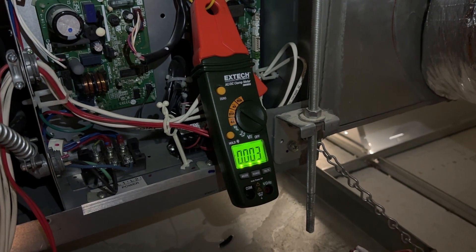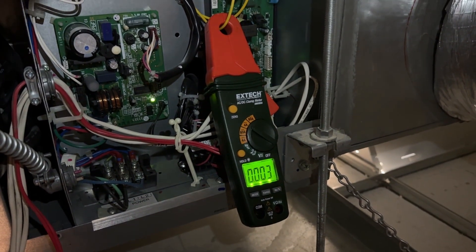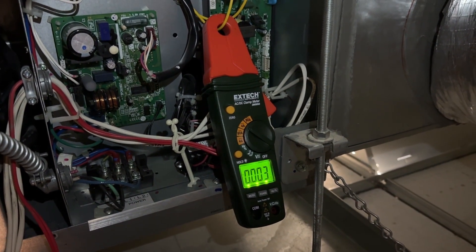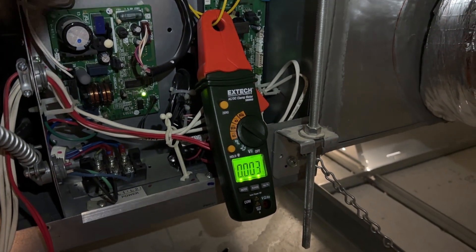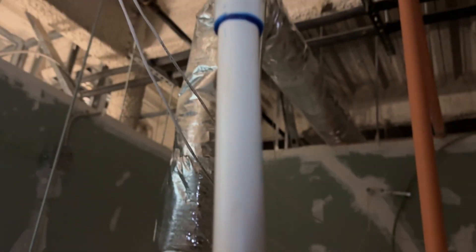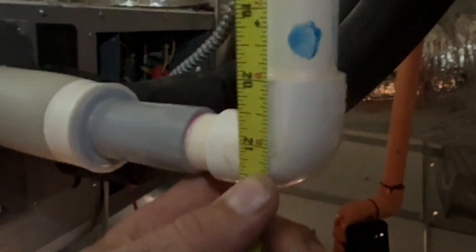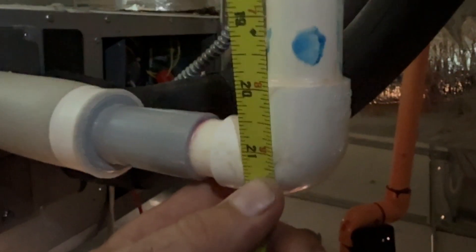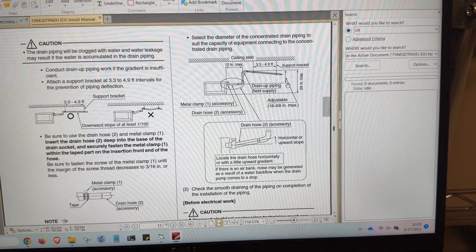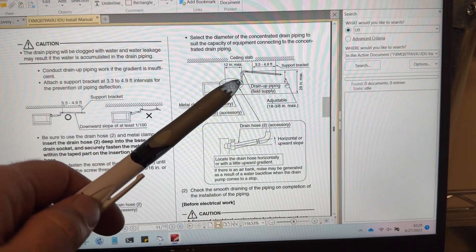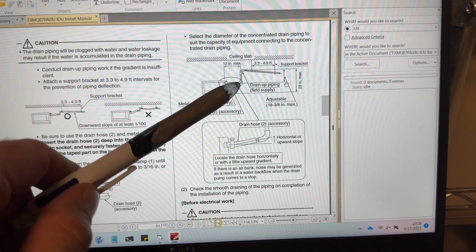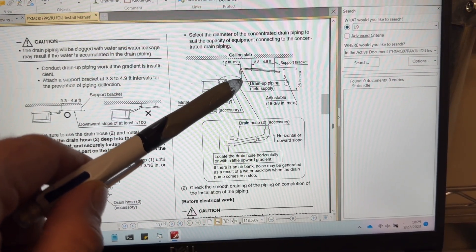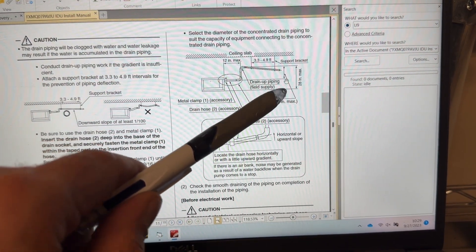The pump does in fact shut off in the off mode. It just runs for a while which makes sense. It's trying to clear the pan but it's never gonna do that when you've got this much rise. Let's see what we have here. 21 inches. Well that is the problem. I know that these pumps have some lift but it looked too much to me and it is.